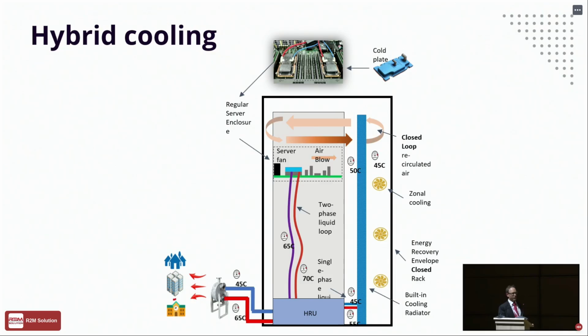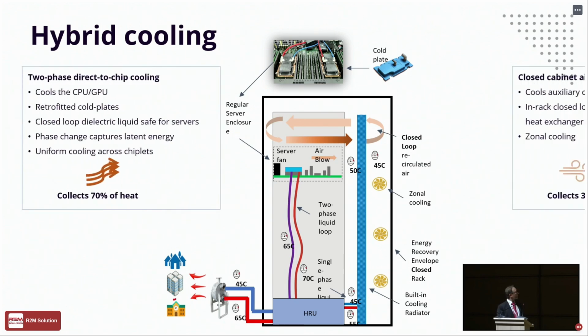There's another part which is air-cooled—everything is in a closed rack, a closed cabinet, supported with zonal air cooling. We have an orchestration tool, and with this tool and the MOTA algorithm—maximization of waste heat output—we are able to increase the waste heat output on demand. Depending on where we orchestrate within the rack, we can achieve higher temperatures or higher heat output, or less if needed.